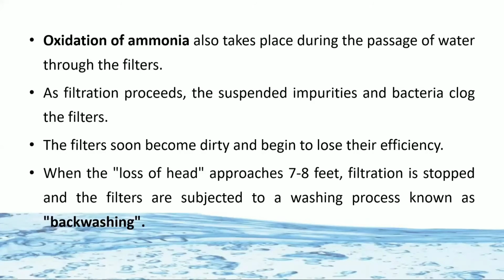Filters get clogged, blocked. So when there is a loss of head and that block is up to 7 to 8 feet, the filtration should be stopped and the filter is subjected to washing. That washing process is known as backwashing.